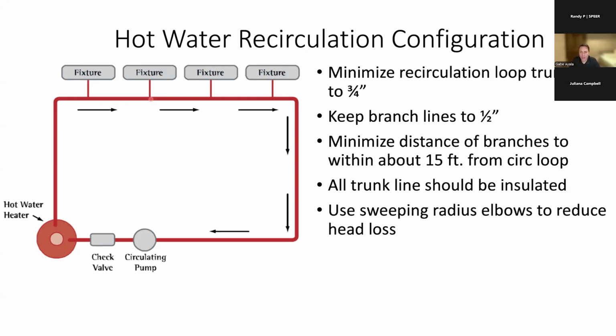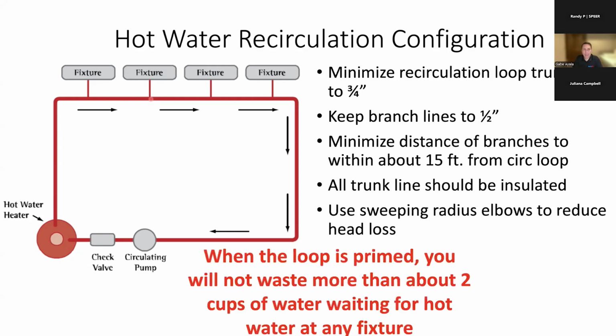And then also try to avoid hard 90 elbows. This is more of a guideline for the plumbers to follow, but you want to use more sweeping radius elbows versus hard 90 elbows. That increases circulation performance and reduces head loss. So when the loop is primed, you're not going to waste more than about 2 to 3 cups of water waiting for hot water at any fixture.